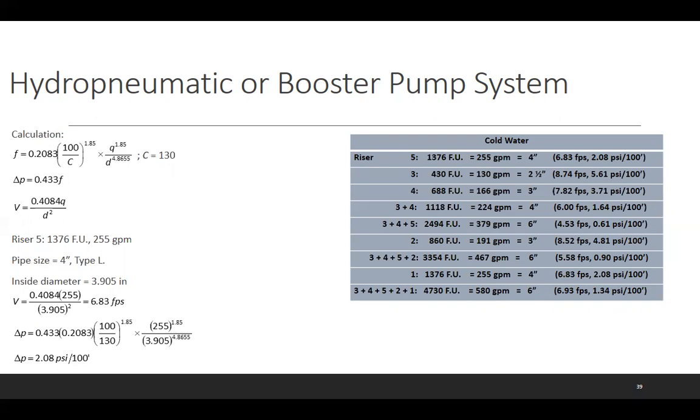C is equal to 130 for copper pipes. Sa plastic, iba naman ang value. So, pag gawin mo to sa PPR o yung polypropylene plastic na ginagamit dito sa Pilipinas na for hot and cold, hanapin mo yung C value niya. So, ito lang yung insert mo dito. Plus, siyempre, yung inside diameter, standard na.